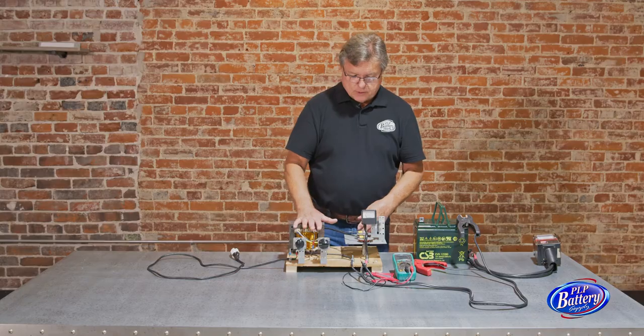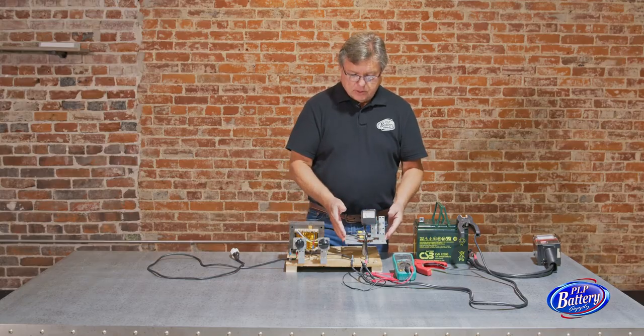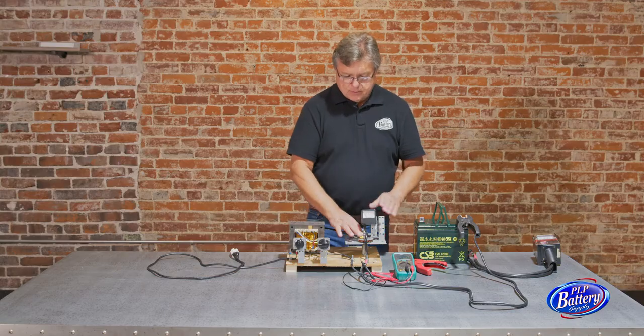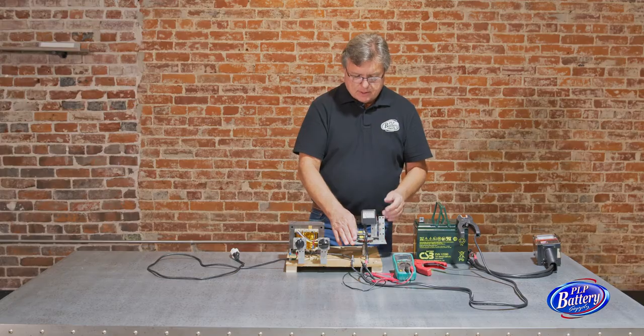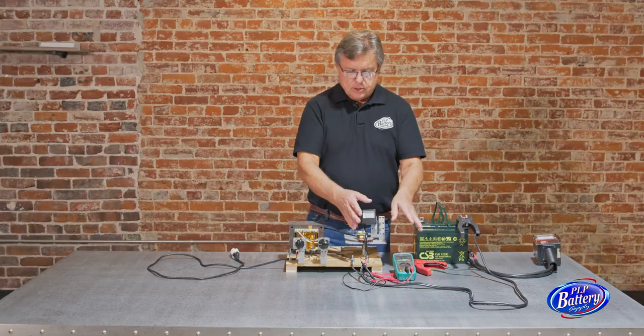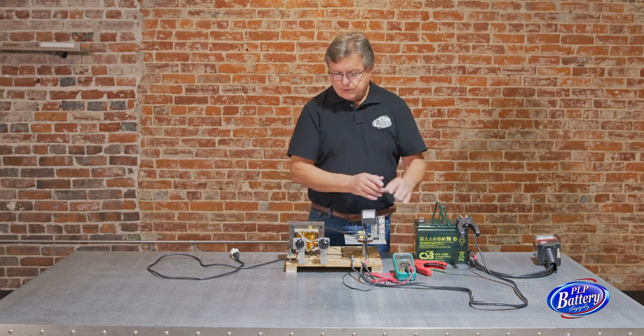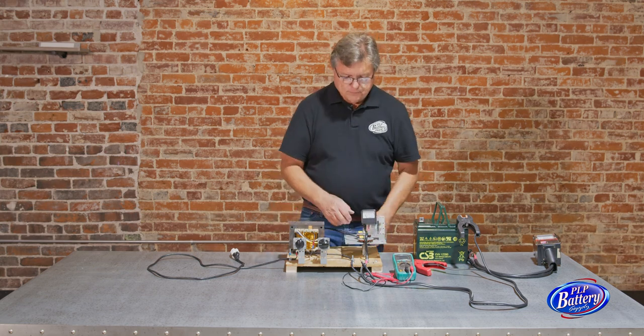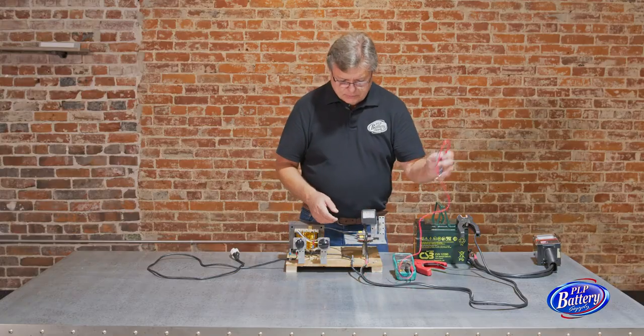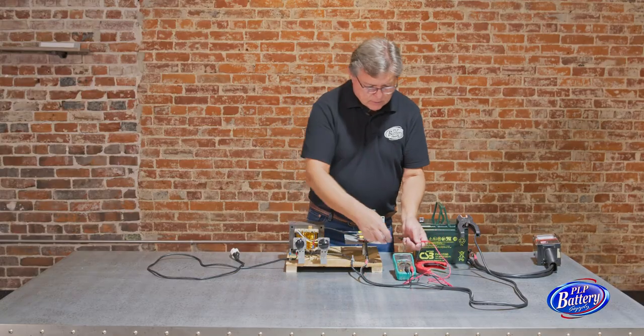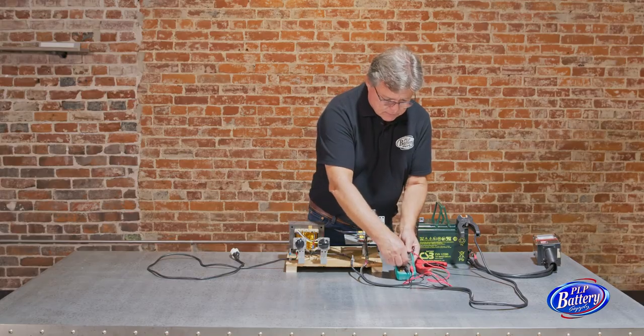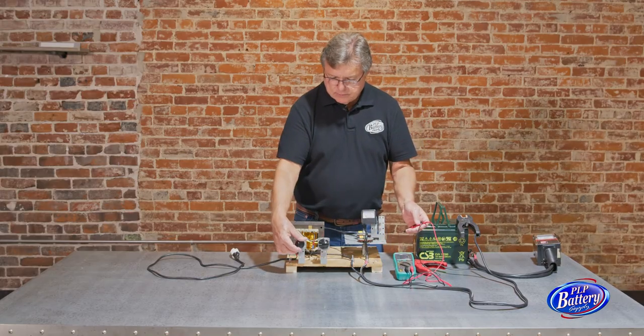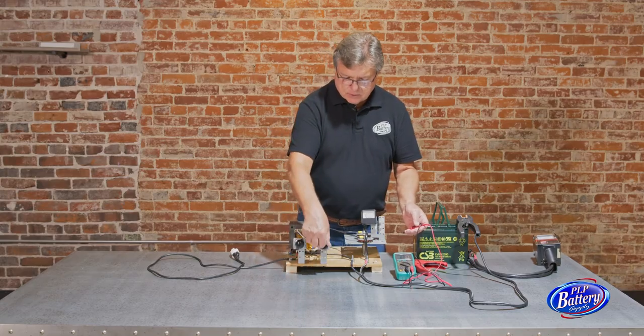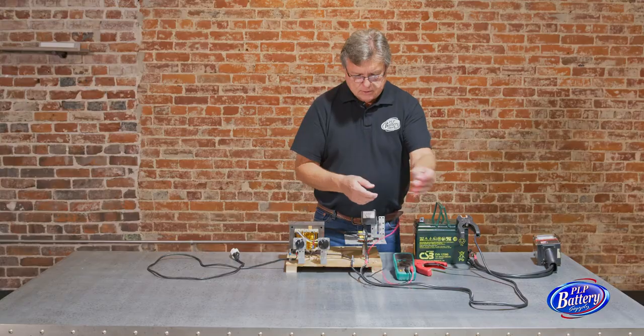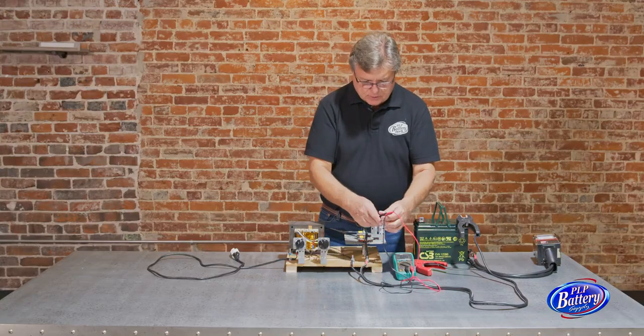So once we know that's working, then if we have a fault, we know that whatever the problem is, it is from this point outward. So it's going to be from the rectifier out. The rectifier, the breakers, the meter, a connection, a clamp. It's somewhere out there because this part is all working. And if we do another test to check that stuff, we can do that even. Again, we're going to leave it turned on. We're going to turn on to our first setting on the transformer, and then we're just going to check here.